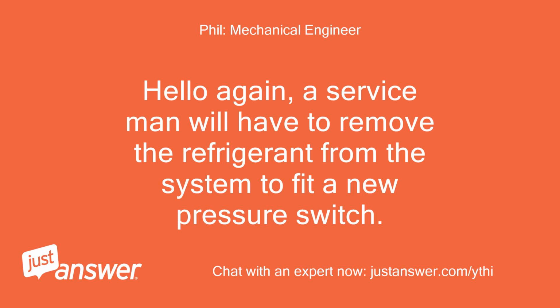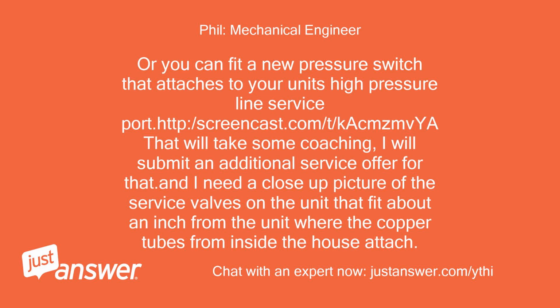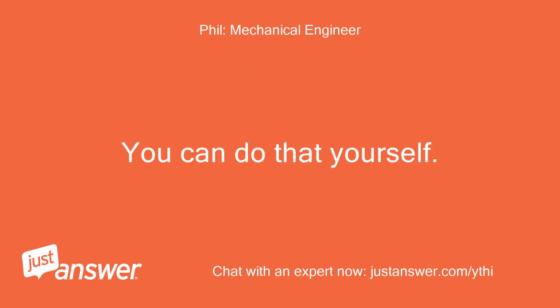Hello again. A serviceman will have to remove the refrigerant from the system to fit a new pressure switch. Cost in the $400+ range. Or you can fit a new pressure switch that attaches to your unit's high pressure line service port. That will take some coaching. I will submit an additional service offer for that. And I need a close-up picture of the service valves on the unit that fit about an inch from the unit where the copper tubes from inside the house attach. You can do that yourself.